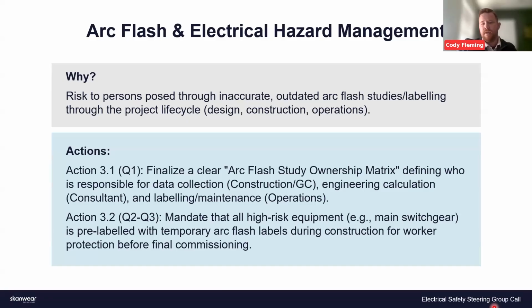Another story: you'll get your calculations from an engineering firm, KW, whoever it might be, or maybe your own internal engineering teams. But that doesn't necessarily mean the equipment can be set that way. I've seen certain make/model breakers where the variability in current ratings changes the higher you go. So let's say your instantaneous current setting needs to be 15,000 to 15,500 amps. However, certain makes and models can only go in 1,000 amp increments once past 10,000. So how do we account for that?